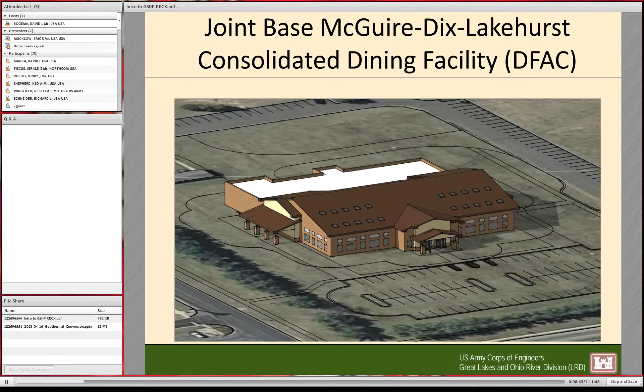This will have a geothermal well field designed to accommodate 100% of the building load. There will be 60 boreholes, each with a depth of 500 feet, with a spacing of 20 feet from one borehole center to the other. The system will be served entirely by ground source heat pumps with a makeup air unit, which also receives water from a water-to-water heat pump.